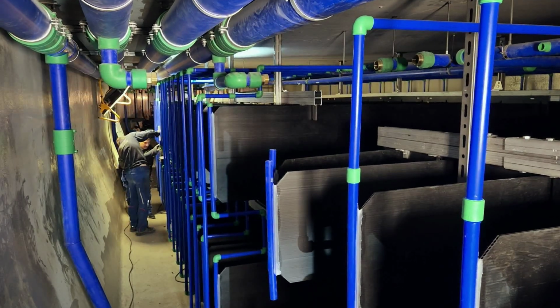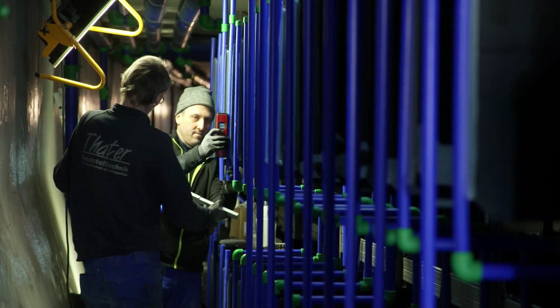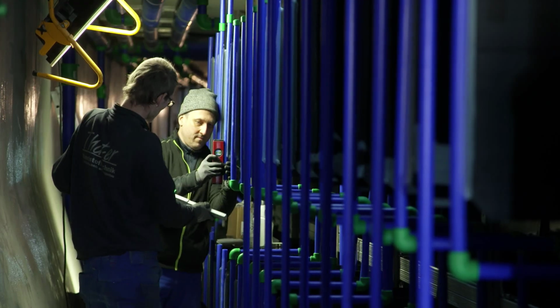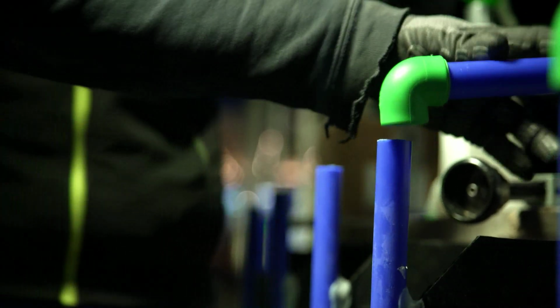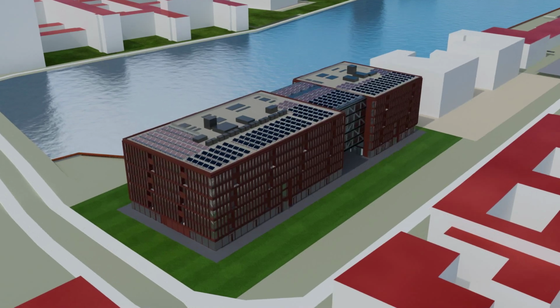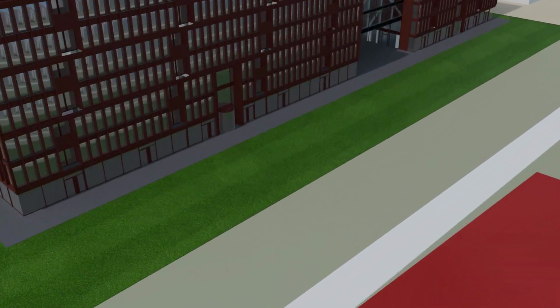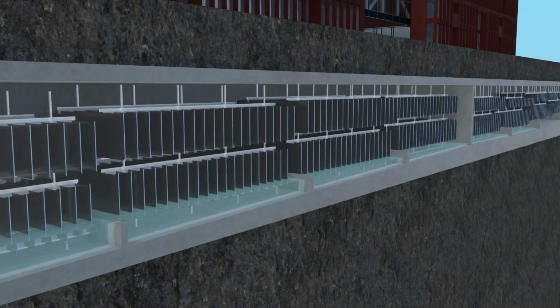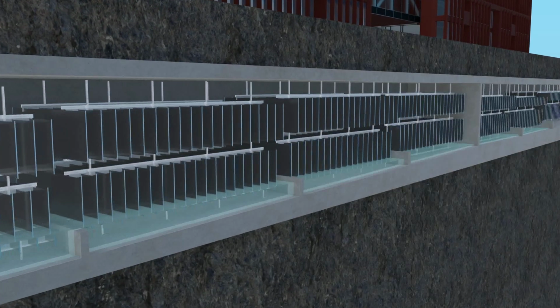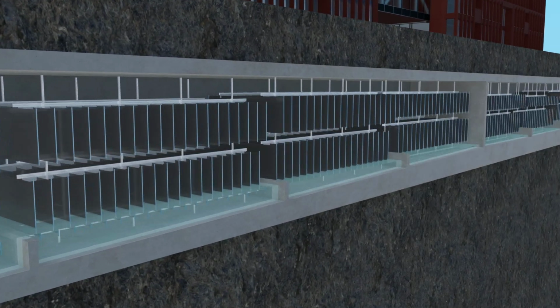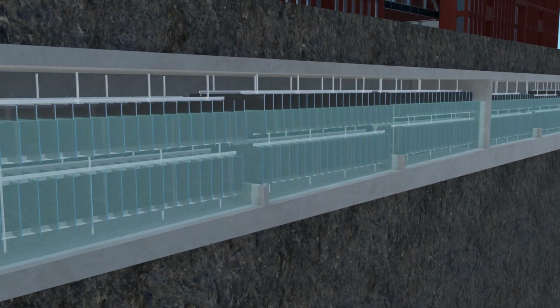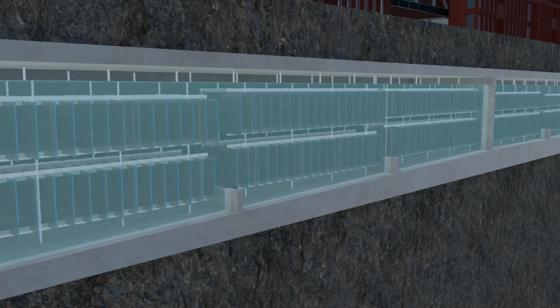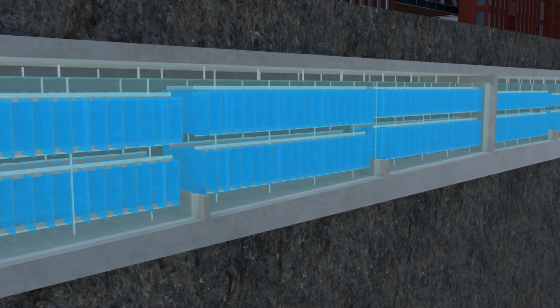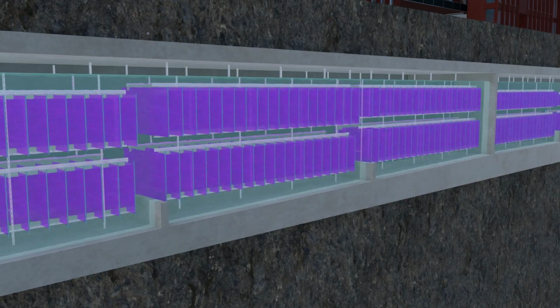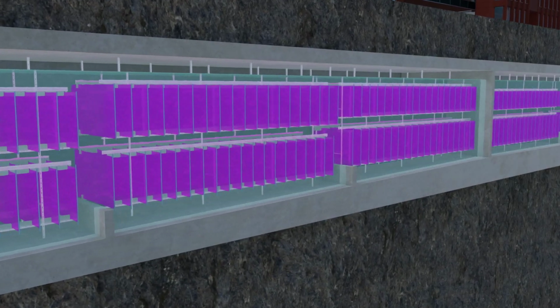A water glycol mixture, known as brine, flows into the plate heat exchangers via a pipe system that is several hundred meters long. Both heat and cold can be stored in the tunnel. The plate heat exchangers are located in the storage tank directly next to the building. Once the construction work is completed, the tunnel will be flooded with water. The water glycol mixture then flows through the inside of the heat exchangers. In the summer, the brine transports heat from the building into the storage tank. The storage tank next to the Spree River was sunk into the groundwater.